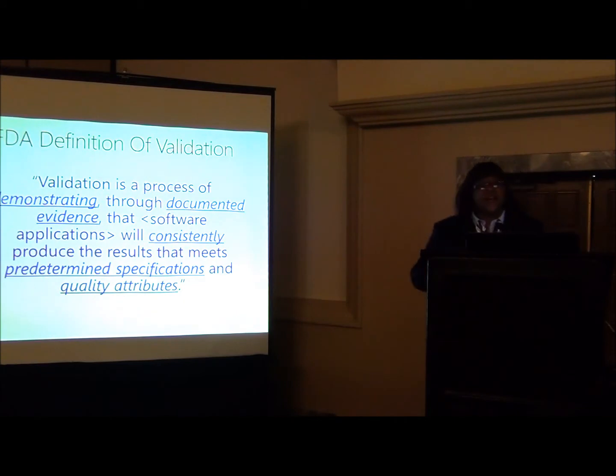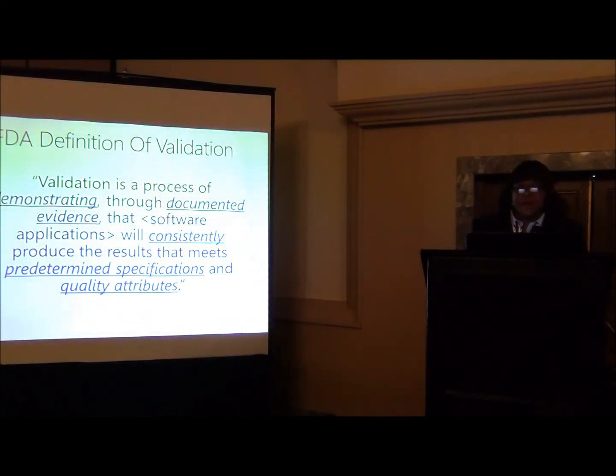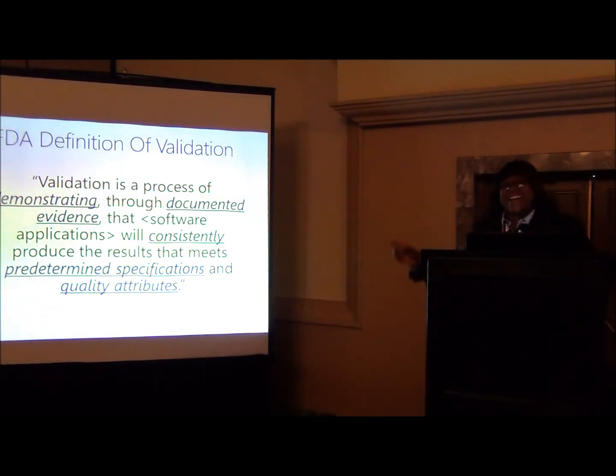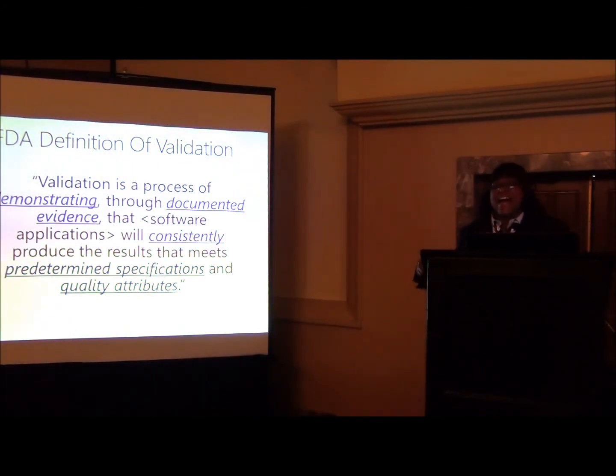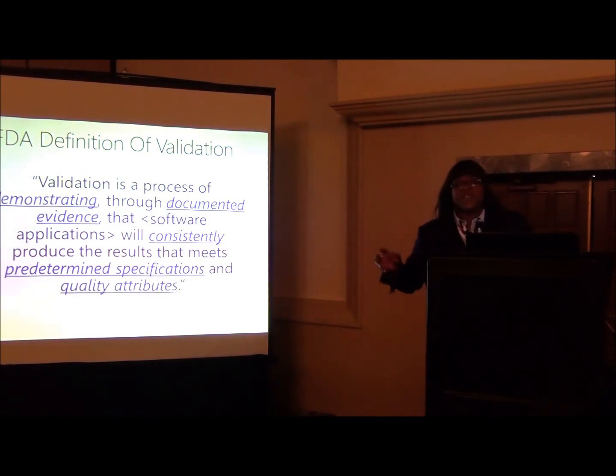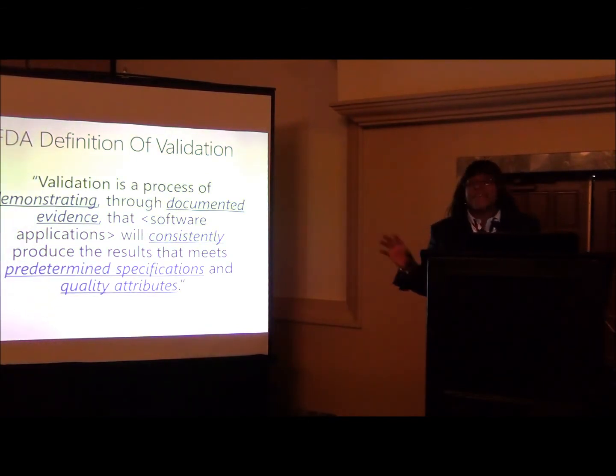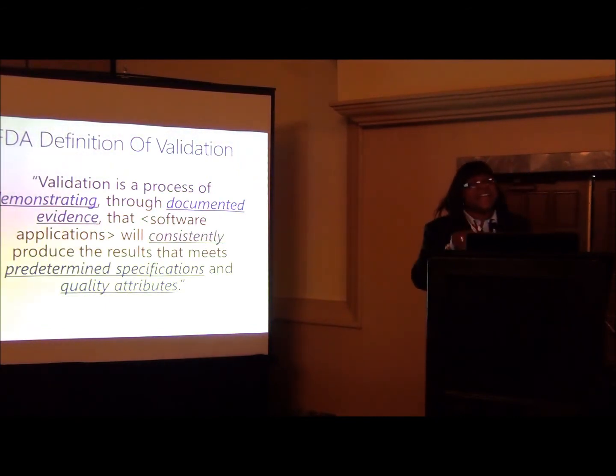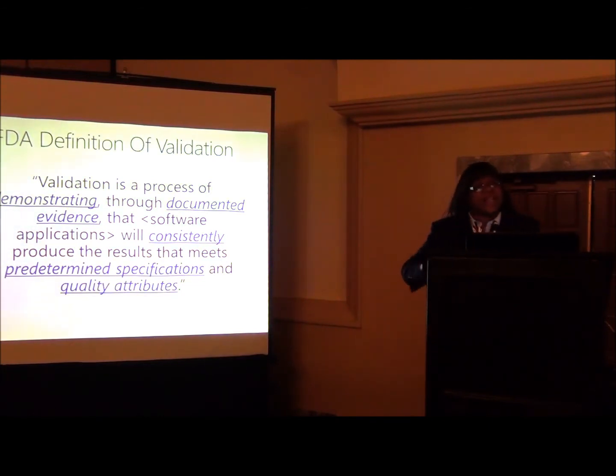What's the definition of validation from the FDA's perspective? It's a process. Validation is not IQ, OQ, PQ. Some people already know those terms and think validation is all about testing. Testing is a part of validation, but it is not validation in and of itself — it's just part of it.